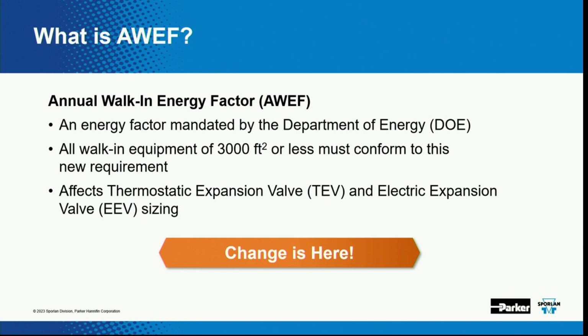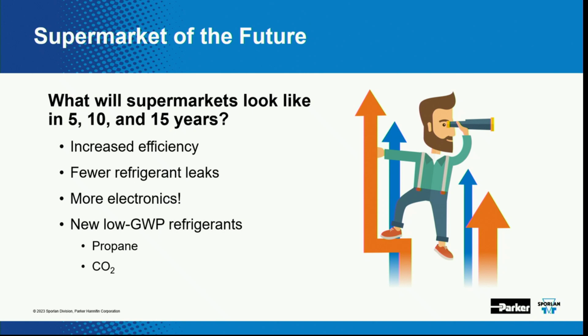Annual walk-in energy factor, AWEF. This is for walk-in coolers, freezers, anything 3,000 square feet or lower. The Department of Energy has mandated that you've got to satisfy their energy requirements, whether it's a new install or a retrofit, and a lot of times that affects the selection of the expansion device. It's something like a SEER rating for walk-in refrigeration and freezers. I'm not going to go into more on that, but it's worth noting.